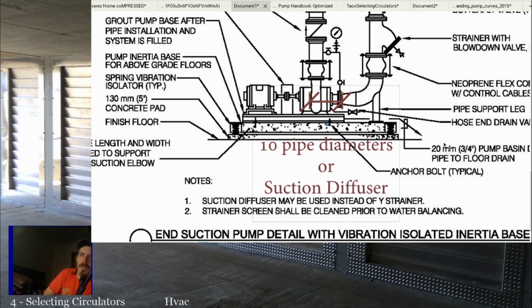Pro tips, suction diffusers usually have a strainer built into them, and there's a strainer that generally needs to be removed after startup. So they'll put a strainer in there to collect any big debris so it won't damage the suction diffuser when you first start it up. And then you're supposed to take that mesh strainer out after the system's circulated for a day or so, and then remove that permanently. And then there's a bigger strainer in there with bigger mesh in it that's permanent. So if you don't do that, a lot of times they'll end up clogged up.